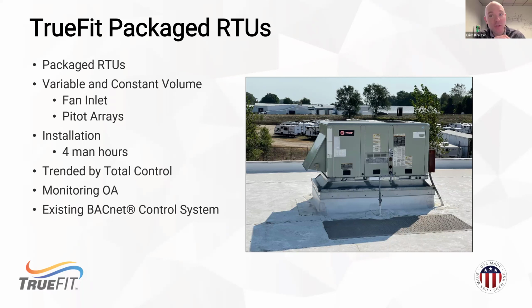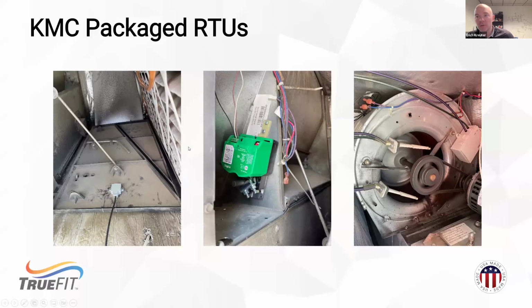We've taken supply air measurements with both fan inlet and pitot arrays. Fan inlet's generally favored. It's easy to get to. It's a very high velocity, very repeatable signal. One of the easiest places for a balancer to calibrate, again, because it's a high velocity, easily accessible application. So installation here on this rooftop was about 4 man hours, and then it was trended, and it's integrated into our building management system here at the office. So a couple pictures here. This one, the inclinometer we see is on that return flap.